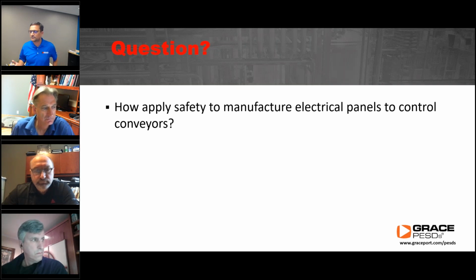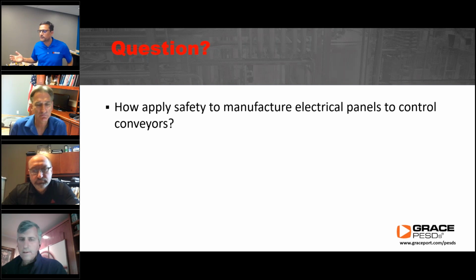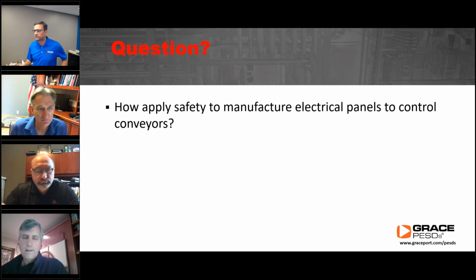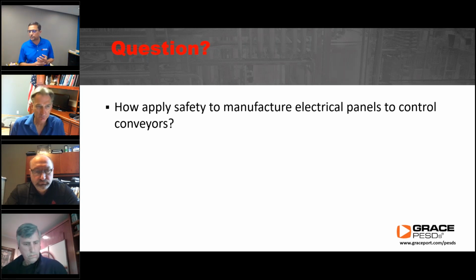The reason I mention conveyor systems and similar control panels specifically is that the technician optimizing these systems may not be a qualified electrical worker, but will still take a quick minute to open the panel, thinking 'I won't be touching the 480 volt or 600 volt system, I'm just accessing the PLC' — which is basically inadvertent contact. Suppose he accidentally touches that energized work. So make sure this person uses safety-by-design controls so he doesn't need to open the panel — that's what some of our products are built to solve.